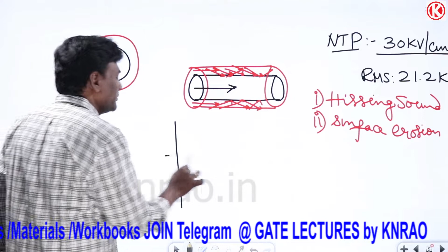Now if I think of this corona, the air around it will break down when the voltage gradient is more than 30 kV per centimeter, because with this analysis you will get a feel for it. So here, 30 kV per centimeter is marked, and then what happens if we think of ionization of air?